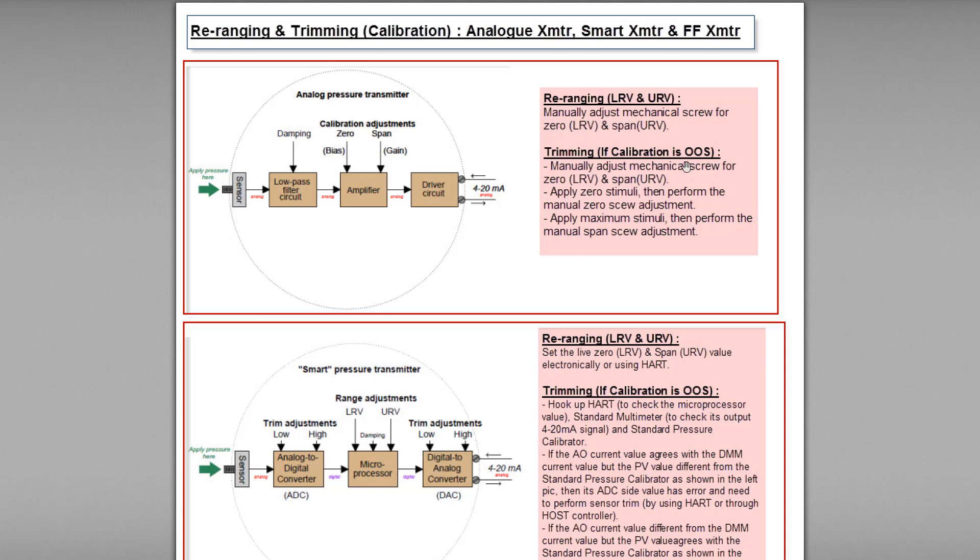To perform calibration adjustment, also called trimming, when the calibration is out of spec or within spec but far from the set point, we have to manually adjust the zero screw and the span screw. The step is almost the same as re-ranging, and it depends on the LRV and URV range.